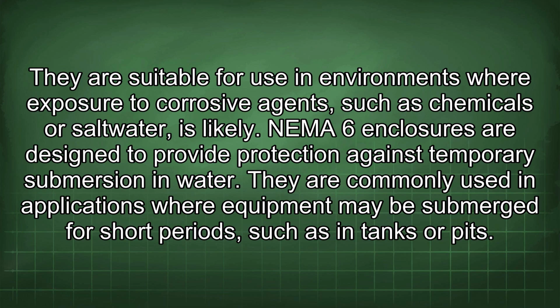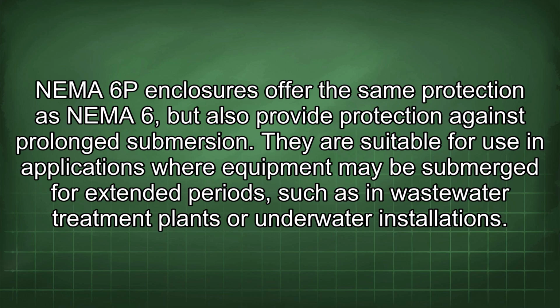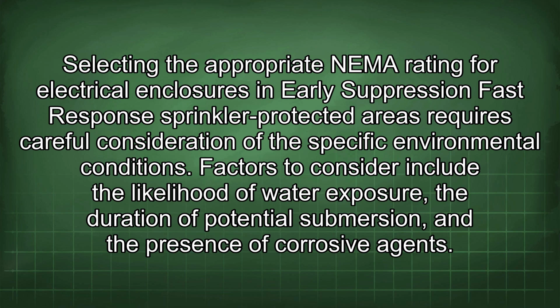NEMA 6 enclosures are designed to provide protection against temporary submersion in water. They are commonly used in applications where equipment may be submerged for short periods, such as in tanks or pits. NEMA 6P enclosures offer the same protection as NEMA 6, but also provide protection against prolonged submersion. They are suitable for use in applications where equipment may be submerged for extended periods, such as in wastewater treatment plants or underwater installations.